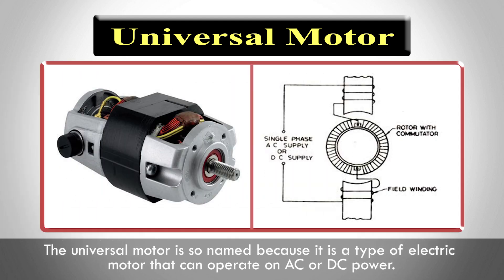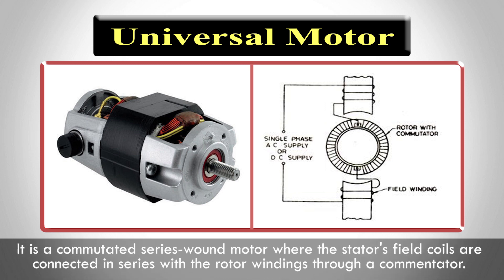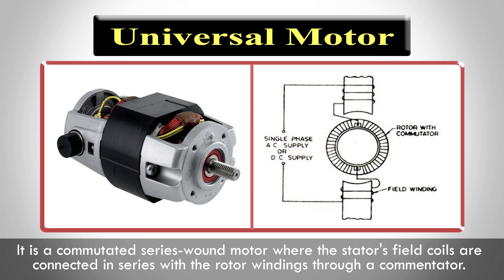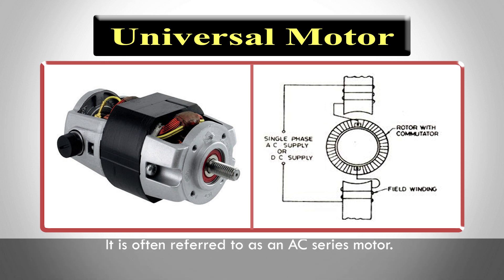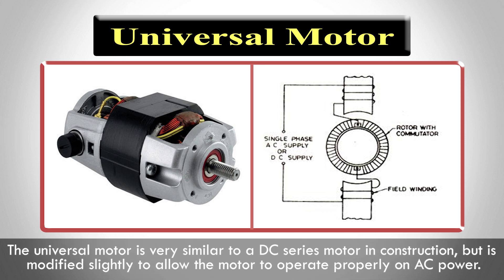The universal motor is so named because it is a type of electric motor that can operate on AC or DC power. It is a commutated series-wound motor where the stator's field coils are connected in series with the rotor windings through a commutator. It is often referred to as an AC series motor, and is very similar to a DC series motor in construction, but modified slightly to allow proper operation on AC power.